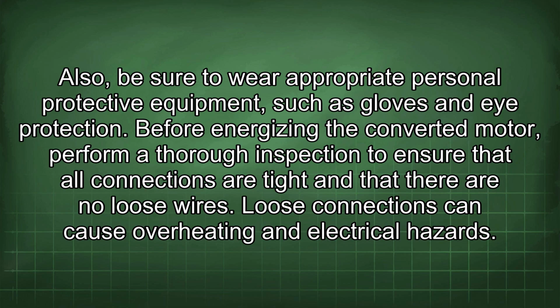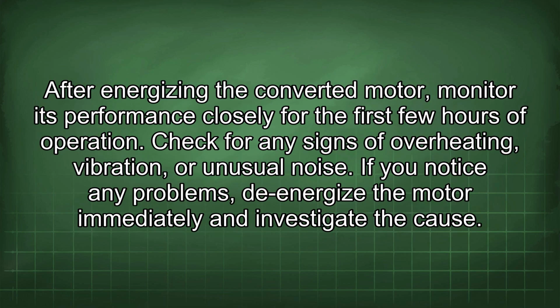Before energizing the converted motor, perform a thorough inspection to ensure that all connections are tight and that there are no loose wires. Loose connections can cause overheating and electrical hazards. After energizing the converted motor, monitor its performance closely for the first few hours of operation. Check for any signs of overheating, vibration, or unusual noise. If you notice any problems, de-energize the motor immediately and investigate the cause.